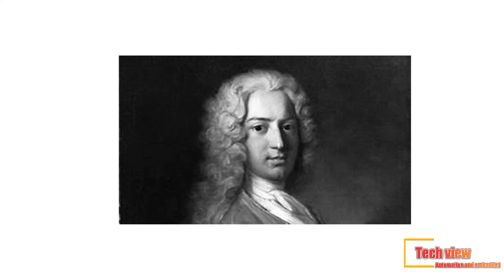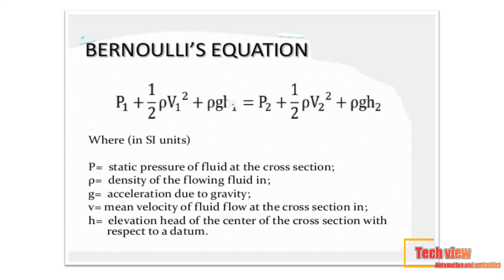Bernoulli's equation states that the pressure drop across the constriction is proportional to the square of the flow rate. Using this relationship, 10% of full-scale flow produces only 1% of the full-scale differential pressure. At 10% of full-scale flow, the differential pressure flow meter accuracy is dependent upon the transmitter being accurate over a 100:1 range of differential pressure. Differential pressure transmitter accuracy is typically degraded at low differential pressures, so flow meter accuracy can be similarly degraded. This nonlinear relationship can have a detrimental effect on the accuracy and turndown of differential pressure flow meters. What matters is the accuracy of the flow measurement system, not the accuracy of the differential pressure transmitter.